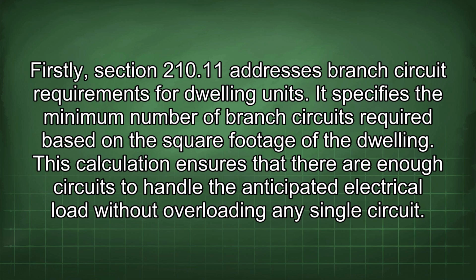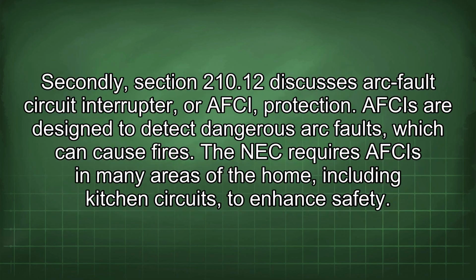It specifies the minimum number of branch circuits required based on the square footage of the dwelling. This calculation ensures that there are enough circuits to handle the anticipated electrical load without overloading any single circuit. Secondly, Section 210.12 discusses arc fault circuit interrupter, or AFCI, protection. AFCIs are designed to detect dangerous arc faults which can cause fires. The NEC requires AFCIs in many areas of the home, including kitchen circuits, to enhance safety.